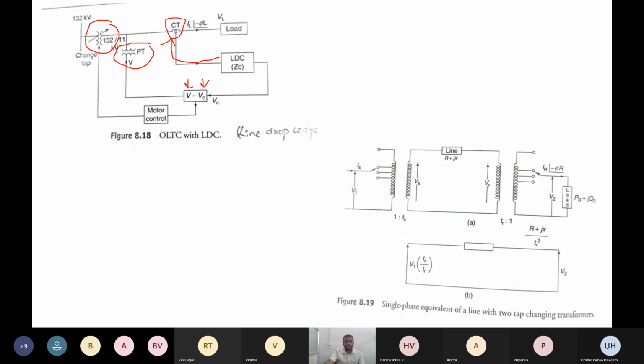So normally you can see 132/11 kV at the distribution transformers. So 132 will be your primary side, that is the HV winding. On the HV winding at 132 kV, we will be having tap changers. So these tap changers, that is S1, S2 position switches, will be controlled by your motors.